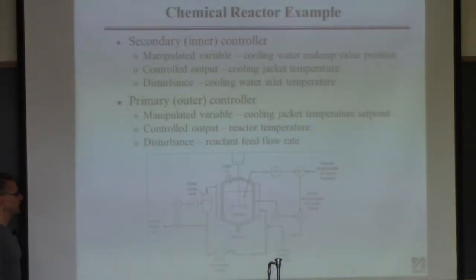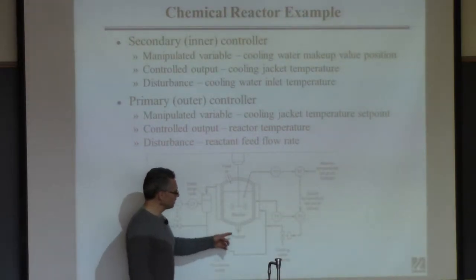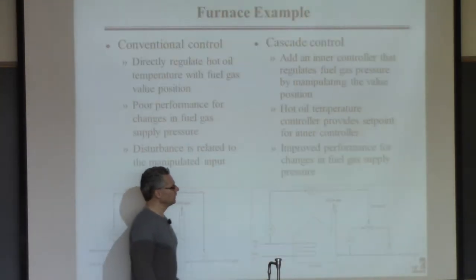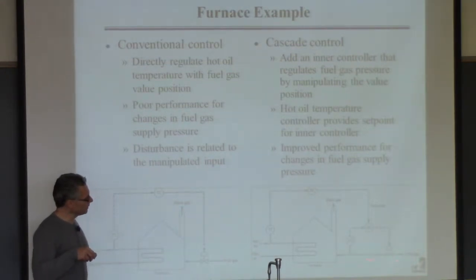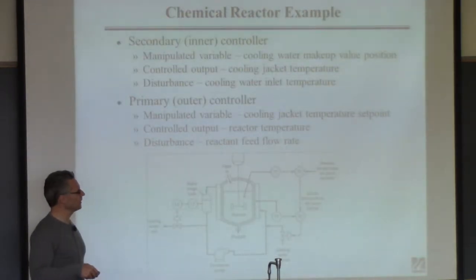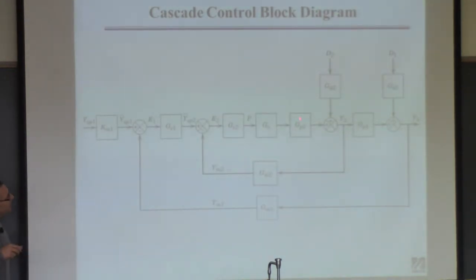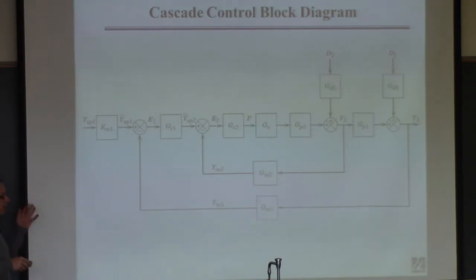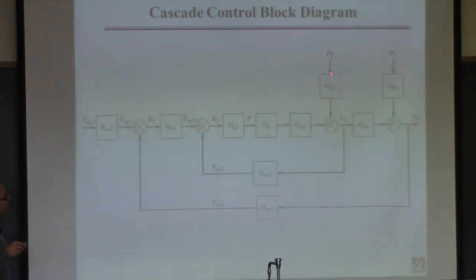This whole idea of cascade control is useful for disturbances that enter the inner loop directly. That's why this strategy works — this disturbance enters the inner loop for cooling water. The disturbance from upstream pressure also enters this inner loop. These are things that affect the inner loop faster than the outer loop, and that's why it works well. Cascade control is going to be useful just for this disturbance — not useful for outer disturbances and not useful for the set point. You have to determine there's a disturbance really causing you a problem and pick a measurement that reflects that disturbance quickly.